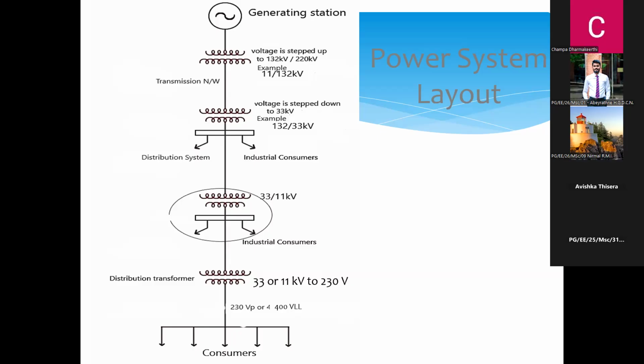And after that, close to the customers, like in villages or in industries, we step down these voltages further from the kilovolt range to the volt range, either 33 kV or 11 kV to 230 volt. We call this happening in a distribution transformer. So at that level, there are customers connected to distribution feeders.